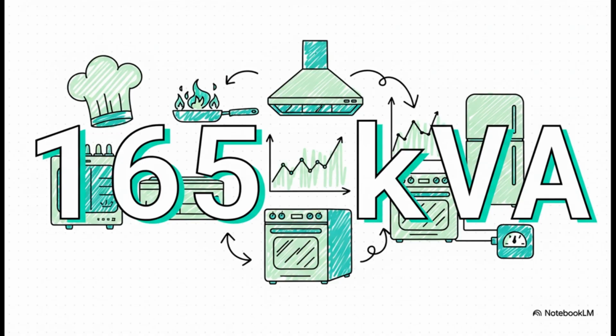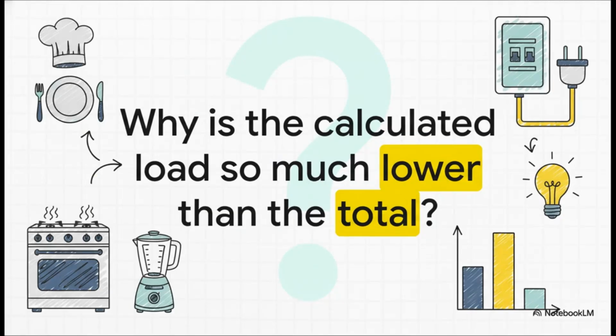200 kVA. Let's look at the mid-range, 201 to 325 kVA. Okay, what happens here? For all electric, the discount gets huge on the additional load. The rule is 10% of the amount over 200 kVA plus a base of 160 kVA. Only 10%. That's a massive 90% diversity factor on that chunk of load over 200 kVA. It is. Now compare that to the not all electric in the same 201 to 325 kVA range.